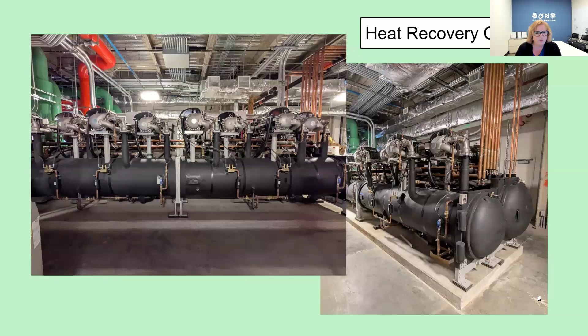Here are our heat recovery chillers—kind of a unique animal. One nice thing about them is that on top of the chiller there are actually 8 compressors, which allows us to dynamically change the load but also provides redundancy. If one compressor goes down, we can isolate it and still use the equipment.